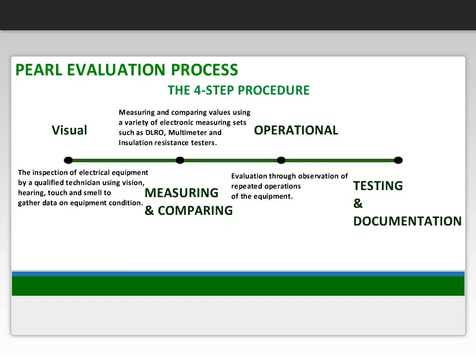The next step involves measuring and comparing values using a variety of electronic measuring sets such as a DLRO, multimeter, and insulation resistance testers. The third step, operational evaluation, is done through observation of repeated operations of the equipment. Finally, testing and documentation needs to be accomplished. It can be done by application of operational voltage and amperes to equipment and recording and comparing the results of the equipment. Now let's turn our attention to the inspecting process.